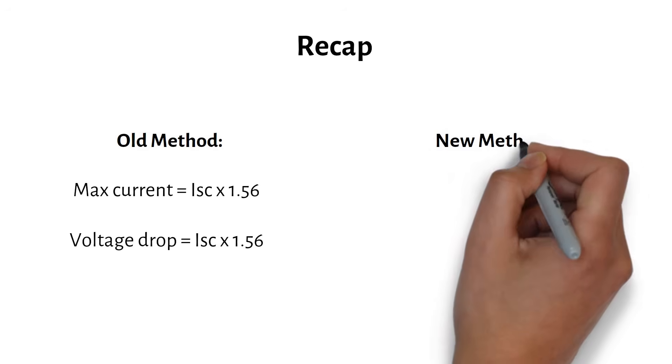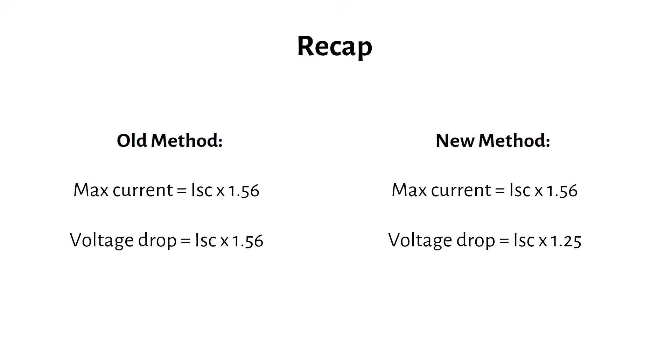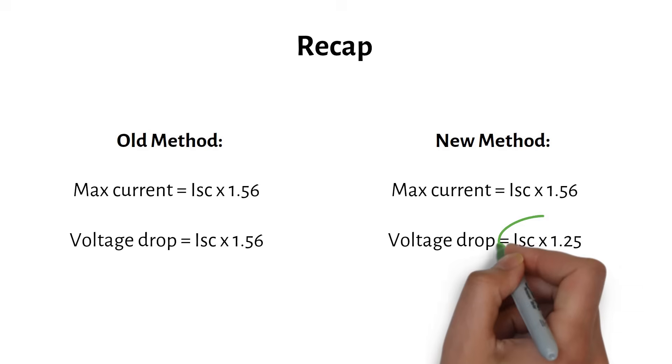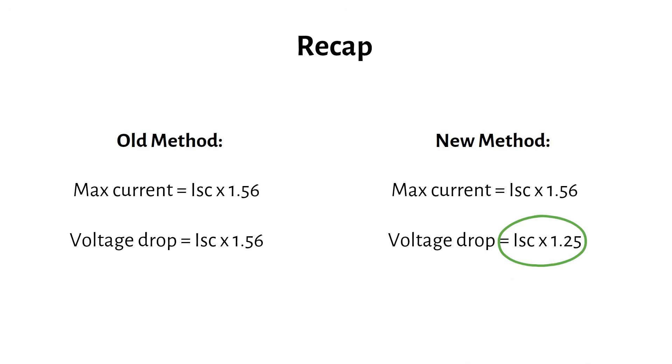So to wrap it up, my old method used the short circuit current times 1.56 for both the max current and voltage drop calculation. And the new method still uses 1.56 for the maximum current, but now I'm using 1.25 for the voltage drop. This often results in smaller PV wire and extra savings while still being safe. Sorry for giving you the wrong information, but I believe this correction was needed.